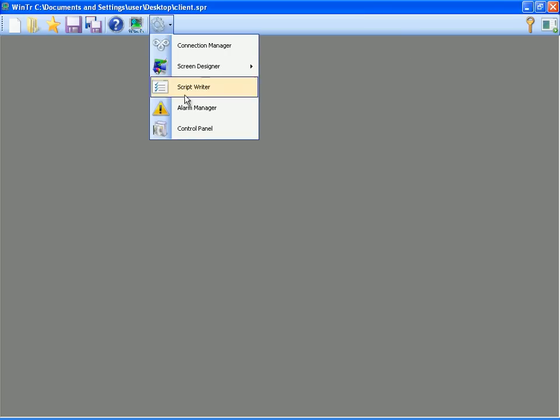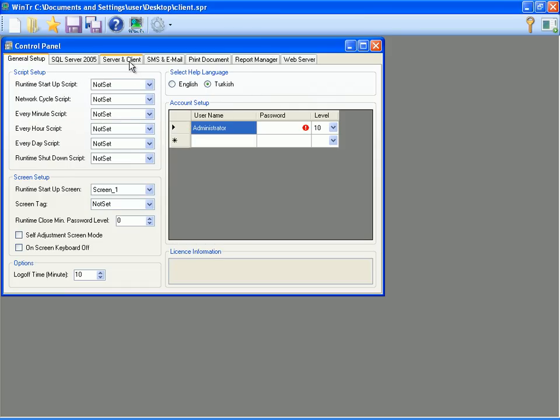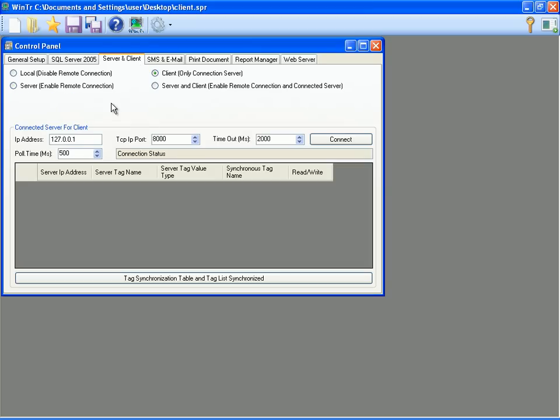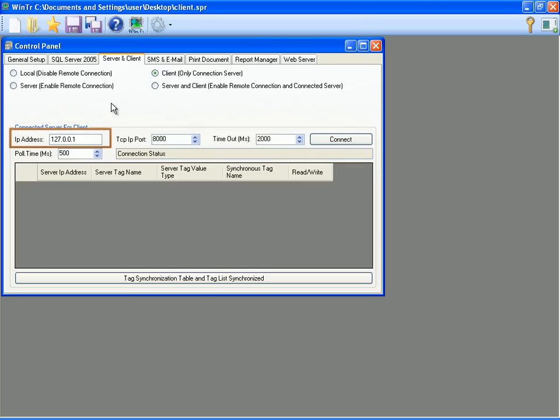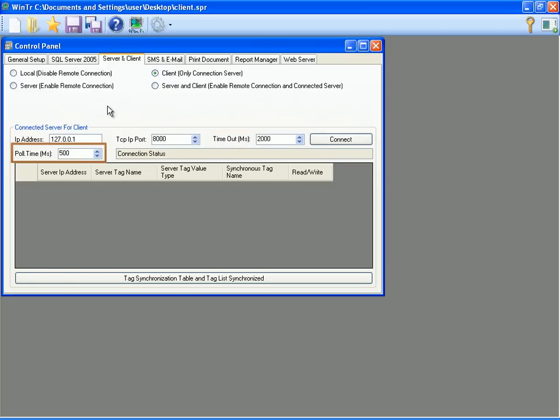Now I am going to determine the project as a client from the control panel server client tab. So I am selecting client option. We are going to make some modifications on connected server for client section. IP address field is the address for the server that will be connected. TCP IP port is the connected port number of the server. Timeout is the period for the establishing connection. Poll time is the waiting period for the next data fetch from the server.